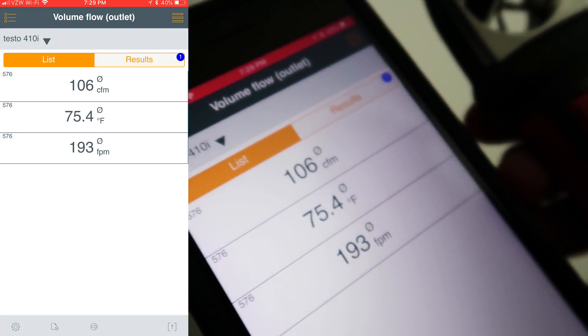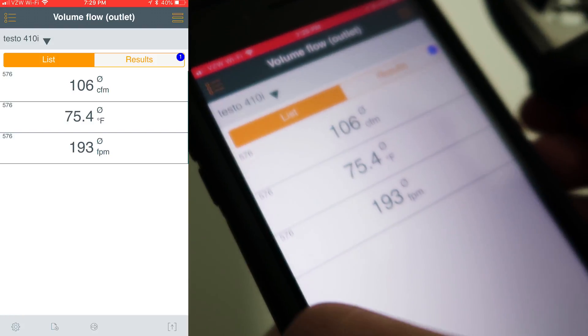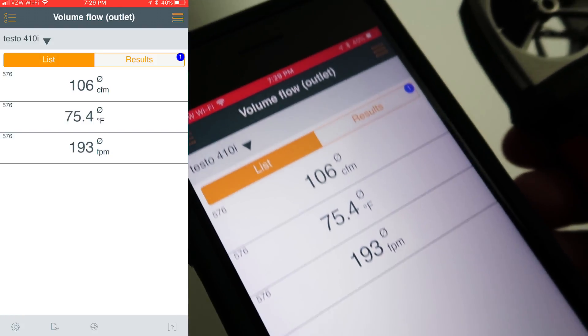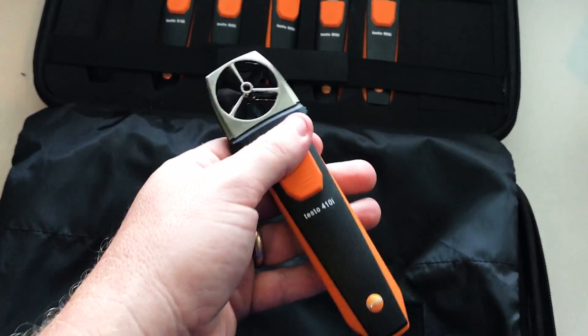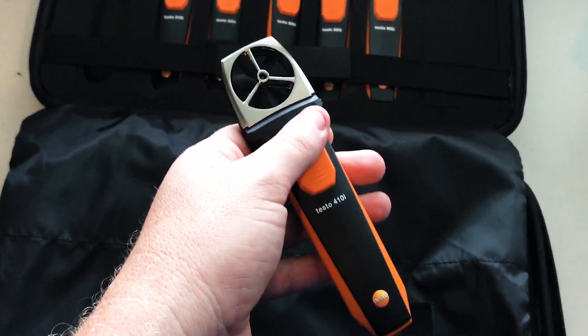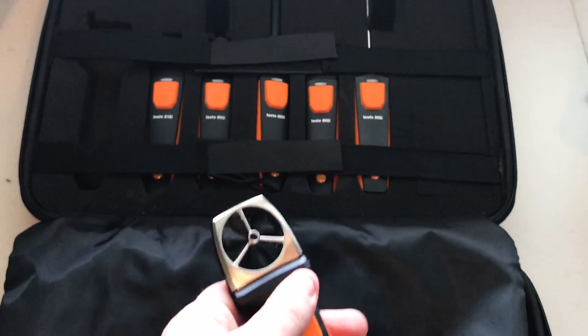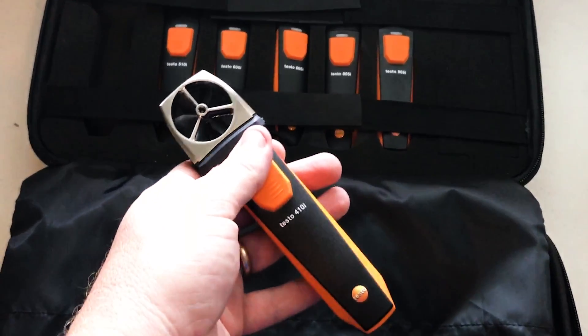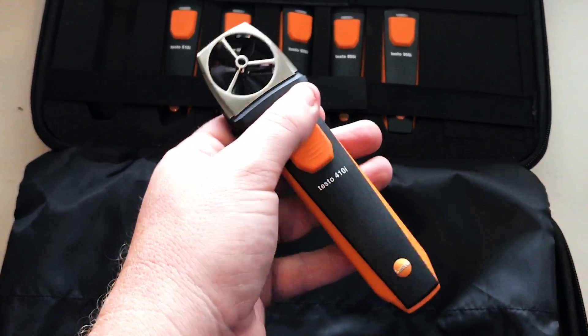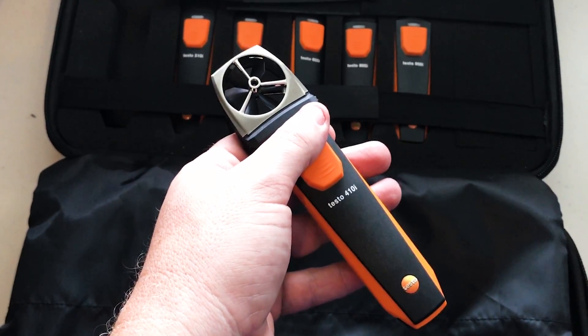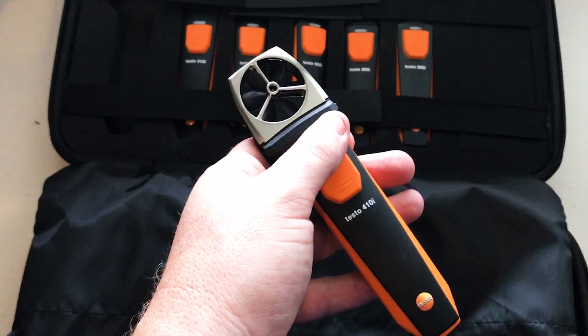In this case, I know that I oversized the duct, but in many cases it would result in not having enough throw. So that's how you can use the Testo 410i, part of the new expanded Smart Probes case, in order to measure airflow at an outlet as well as your velocity. Thanks for watching.